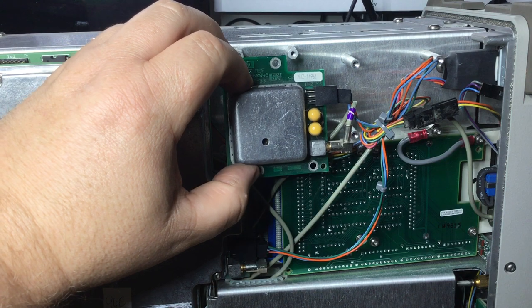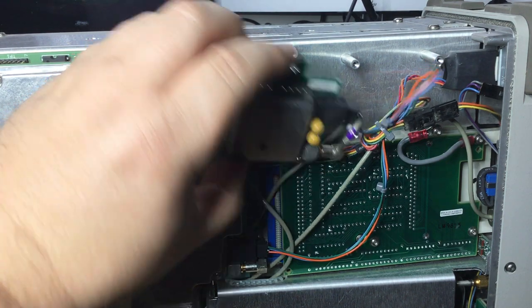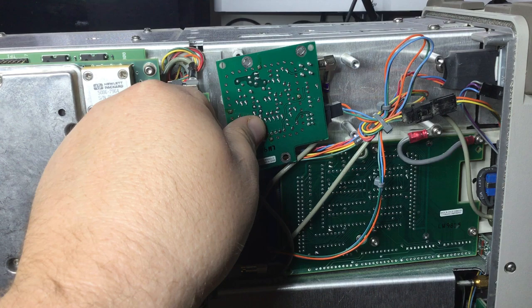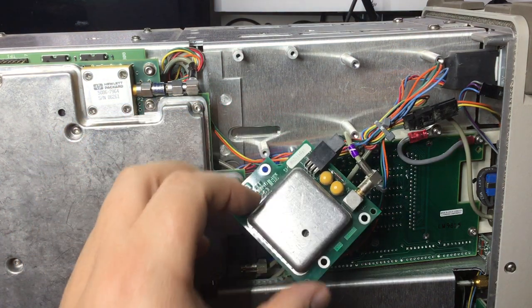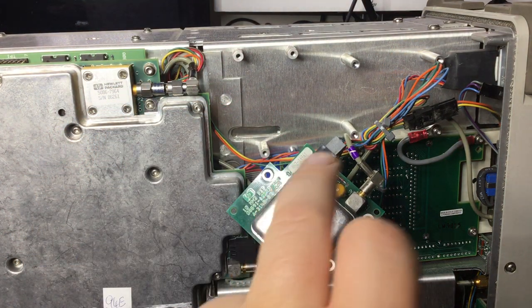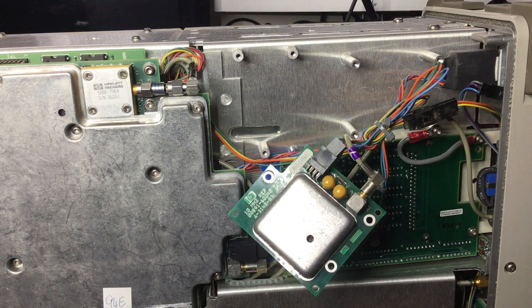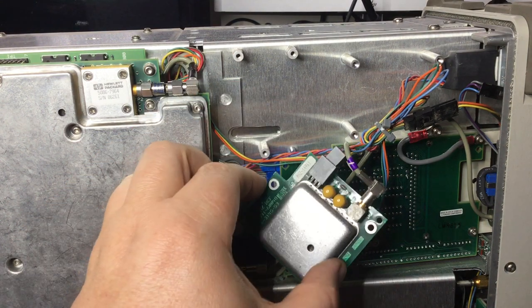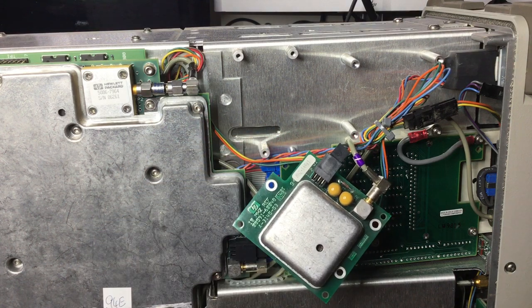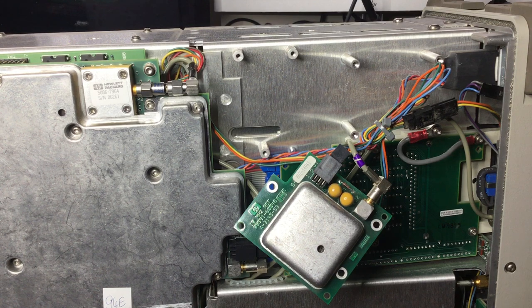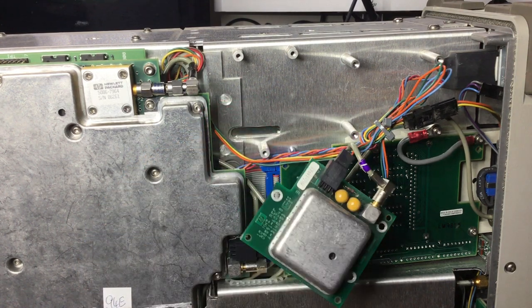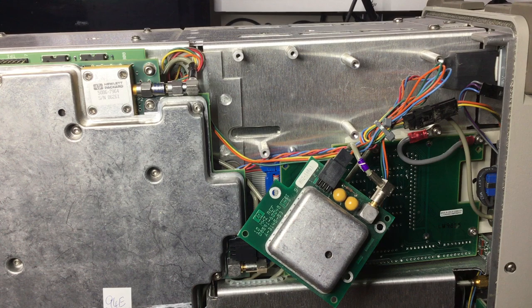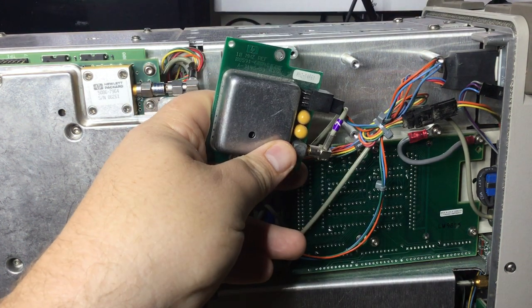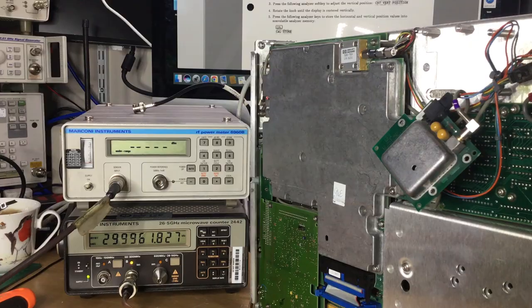So, interesting. Yes, I think it is meant to be that way around, but again, the service manual's a bit misleading, because it seems to indicate there's an adjustment from the bottom of the instrument when it doesn't say having to remove a module, flip it over and then make an adjustment. So I did wonder whether somebody had been messing with it already, which I think is the case anyway, but obviously Agilent may have had a look inside. But I don't think they'd have put anything back incorrectly. I very much doubt it, they'd be experienced. So, interesting. We'll give that adjustment a go.